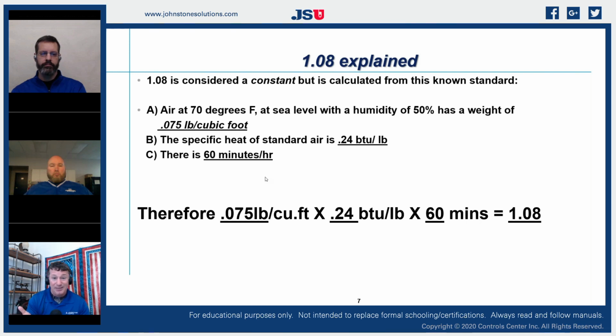It also has a specific heat of about 0.24 BTUs per pound, right? And we know that there's 60 minutes in an hour. So if I'm going to look at the rate of that, I'm going to now be calculating a BTU per hour, because we tend to use that number quite often in our industry, don't we? BTUs per hour. So that's actually what we're doing, is we are coming up with a correction factor for BTUs per hour.